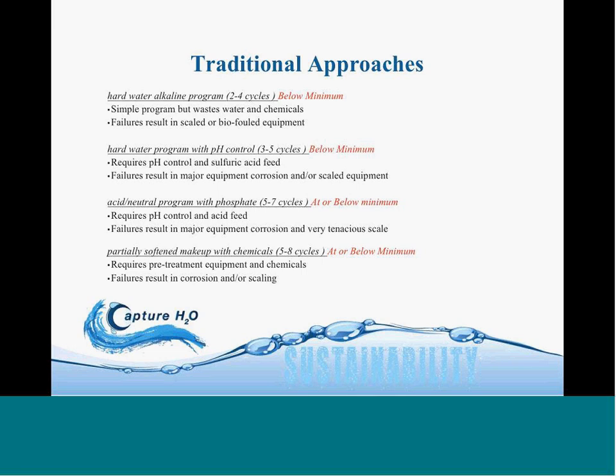You have to pump a lot of chemicals in, and if there's a failure with the system, you get scale and bacteria growth. If you take that same chemistry and you would control the pH by adding acid, you can increase the cycles and reduce the water a bit, but it's still below the minimum. There's other programs that you use. You really lower the pH and use another chemistry.